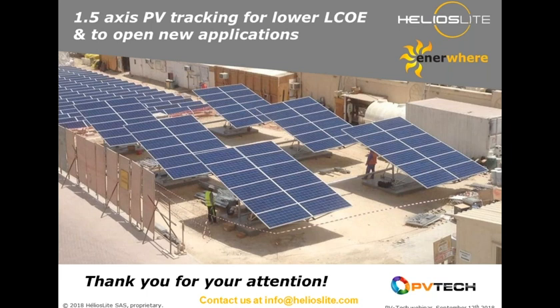So it's very easy to adapt the solution to the soil condition, and for an isolated site you only need a small jackhammer to be able to drive the anchor into the ground. So it's a very interesting solution from that standpoint. And when you pull on the anchor to pivot the head of the anchor into the ground, you actually measure the amount of force that you're able to take on each anchor. So that's the other aspect we like with this solution - you're basically testing every single anchor that you're driving into the ground, which gives you confidence that you'll be able to take the load they're designed to withstand.